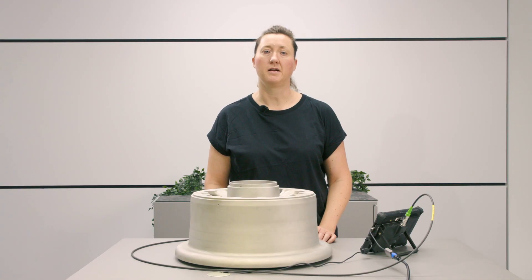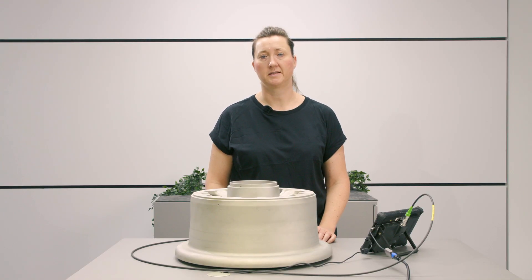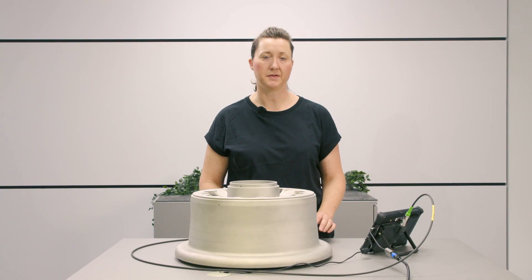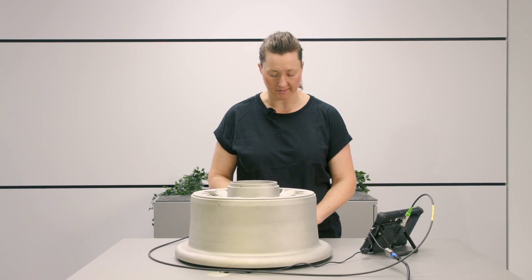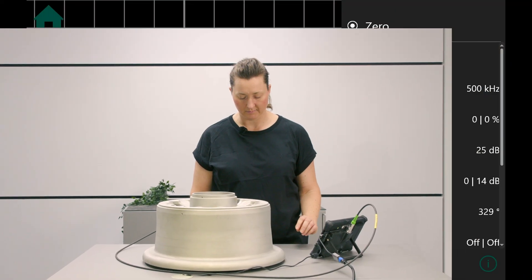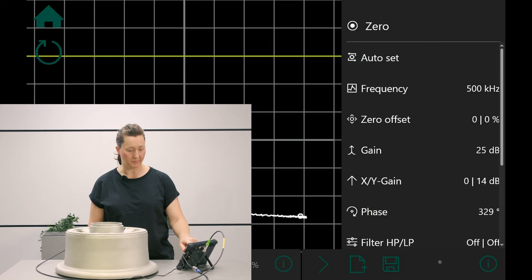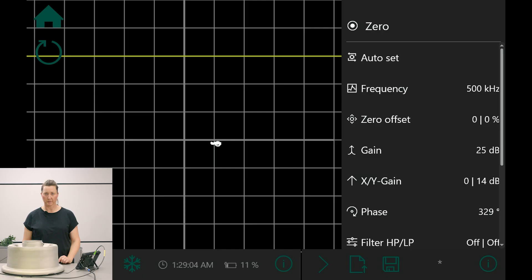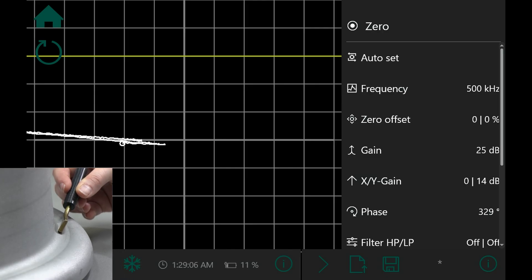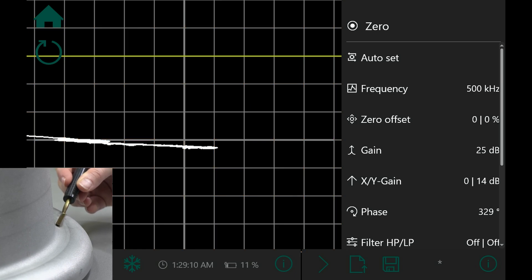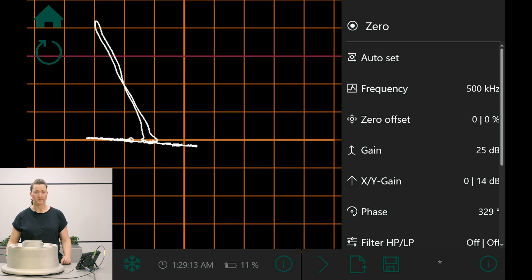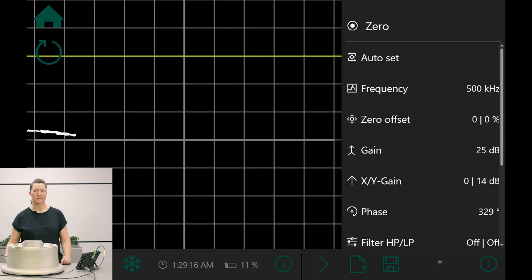Now I will show you crack testing in a real life example. There are some 0.5 mm cracks on the surface. I leave the settings as they are and place the probe on the surface. I press zero and move the probe along the surface. Here I can see the clear crack signal.